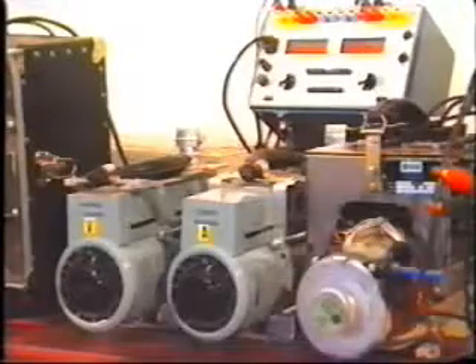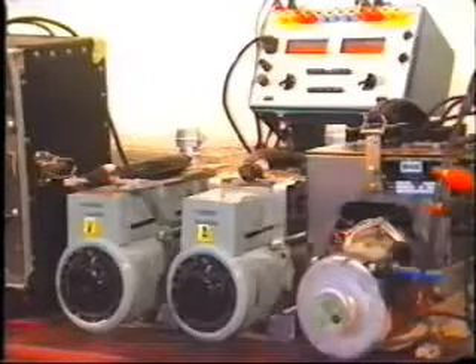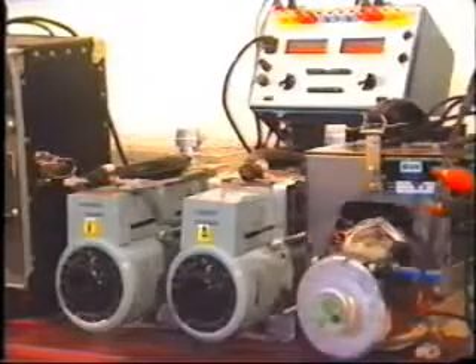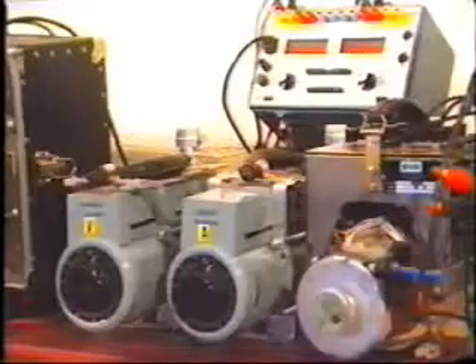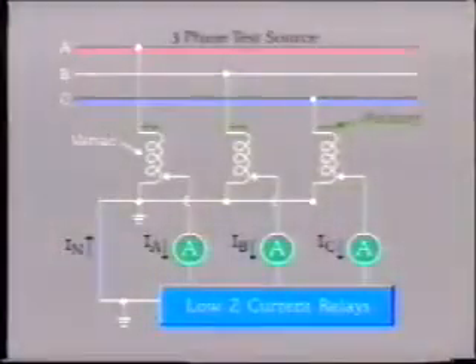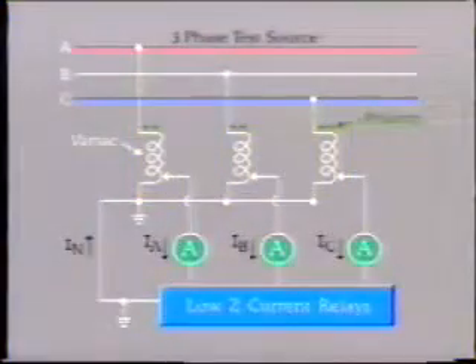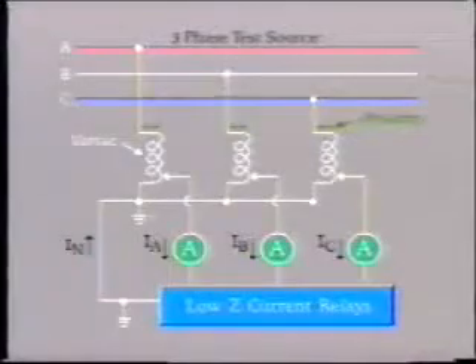Three-phase overcurrent relays, such as pilot wire or negative sequence type, may use a test current setup like this, using variacs and ammeters. Variable three-phase voltage test sources can also be connected in a similar fashion. As always, great care must be taken to ensure that connections are correct. Let's look at this Y connection and see what would happen if we reversed the phase and ground connections to the third variac. With all wipers at their lowest position, we have just applied 120 volts to the low impedance current coil.